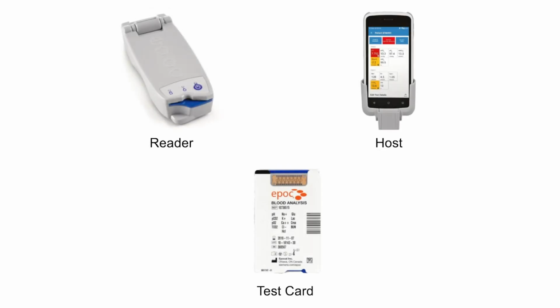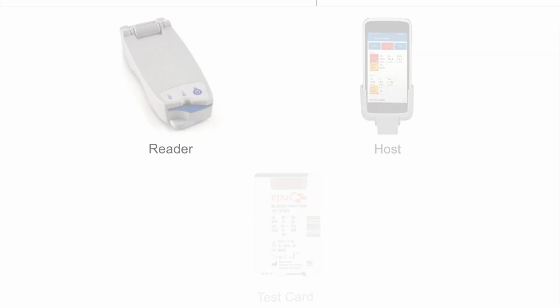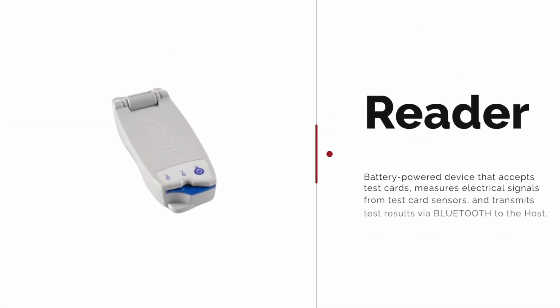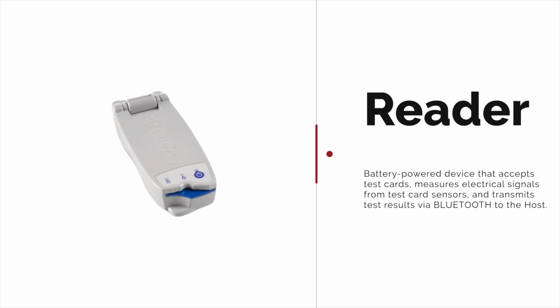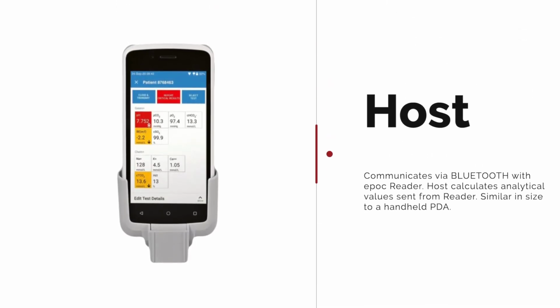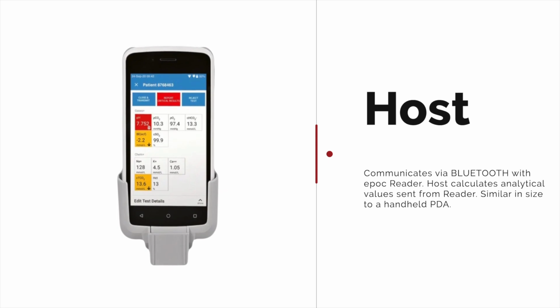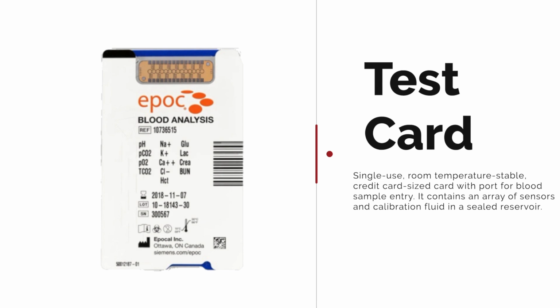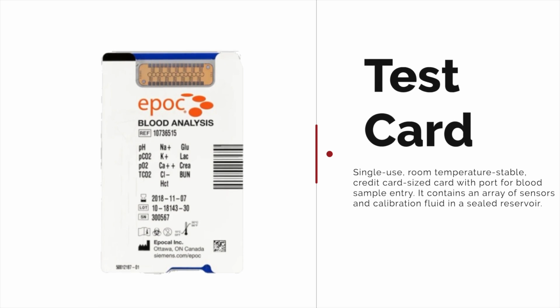The epoc system is made up of three components: the reader, the host, and the test card. The reader is a battery-powered device that actually performs the test. The host is like a tablet. It's where you enter the patient information, control the test, and view the results. And finally, we have the test card, which is single-use and contains necessary sensors and calibration fluid to analyze the sample. The host and the reader work together wirelessly via Bluetooth.